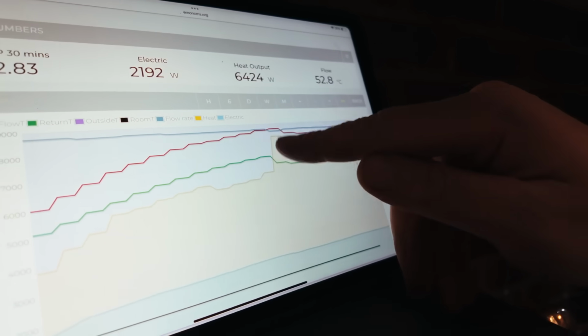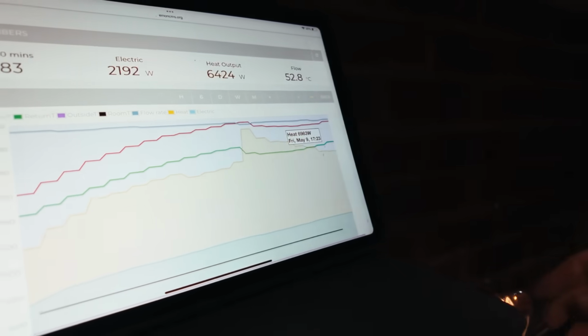Now, I would suggest anyone installing a system like this should size their heat pump for hot water demand rather than heating, and use a 7 kilowatt heat pump minimum, even if your heating power requirement is lower than that. Any efficiency losses from oversizing will be absolutely minimal, as larger heat pumps are usually more efficient anyway. We're testing on a 5 kilowatt heat pump. However, since it's 18-19 degrees outside, the output of this 5 kilowatt unit is equivalent to what a 7 kilowatt unit would be on a cold winter's day anyway.